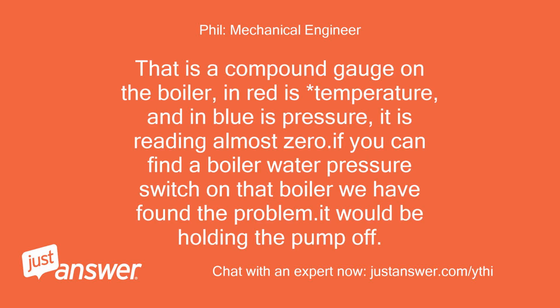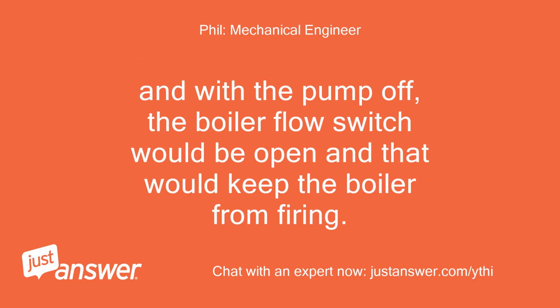That is a compound gauge on the boiler. In red is temperature, and in blue is pressure. It is reading almost 0. If you can find a boiler water pressure switch on that boiler, we have found the problem. It would be holding the pump off. And with the pump off, the boiler flow switch would be open, and that would keep the boiler from firing.